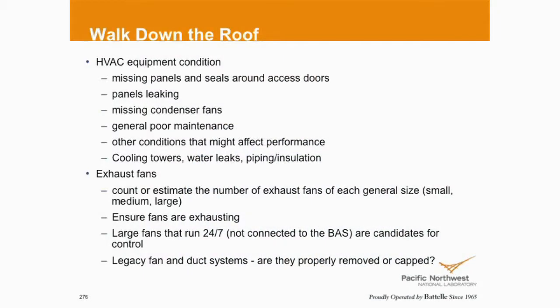Exhaust fans up on roofs. How many exhaust fans do I have? What are they doing? What do they serve? Are they general purpose? Are they on the BAS? Do they run 24/7? If I go down to the electrical room and it's got a motor control center with hand-off-auto switches, how much of my equipment that's on the BAS, and we see this a lot on exhaust fans, is not in auto but is click, click over in hand? Because if they're in hand, they're not going to shut off on my schedule. They're just going to keep running, and I may or may not know about it. Same with pumps and other equipment. So again, we talked about legacy fan and duct systems, so I'm not going to belabor that anymore. Are they removed? Are they capped?